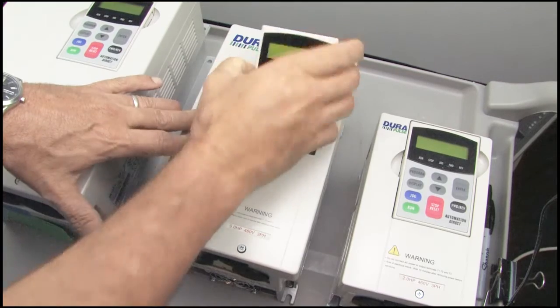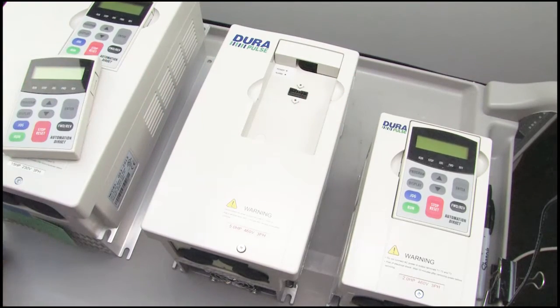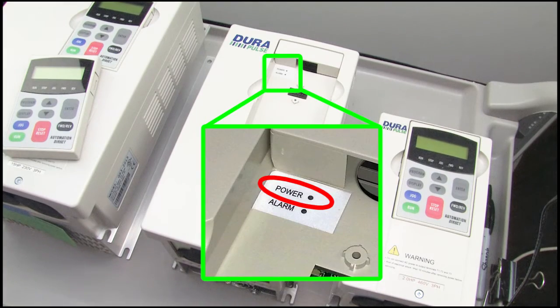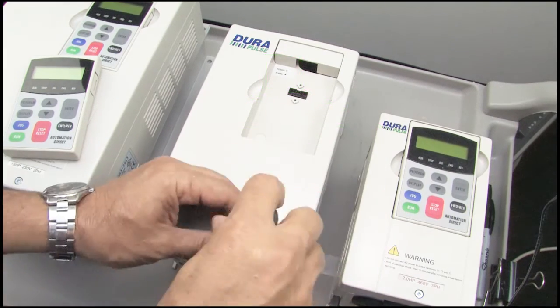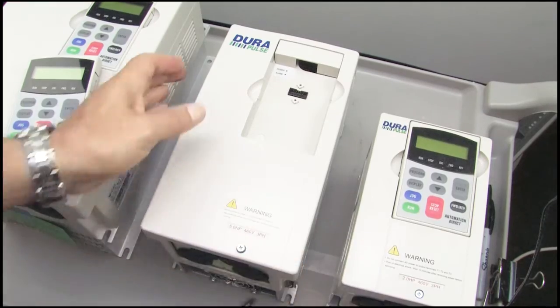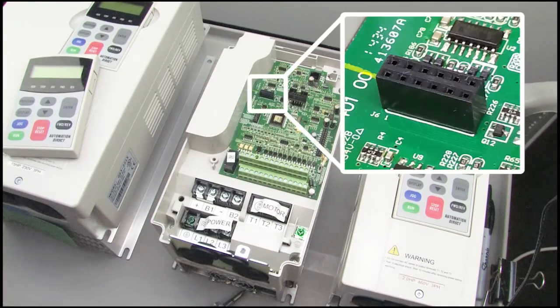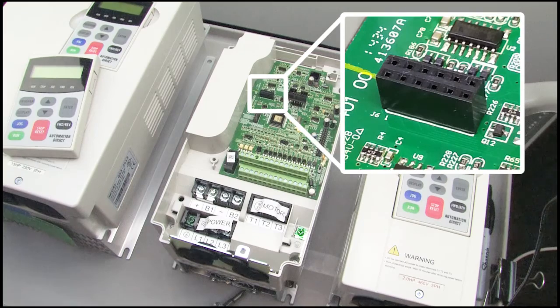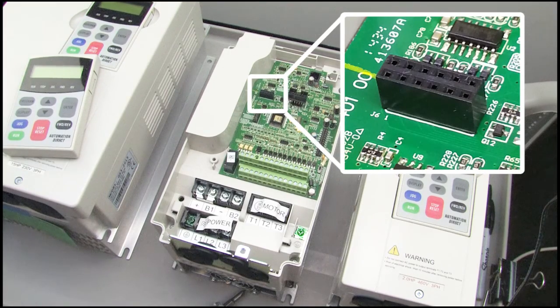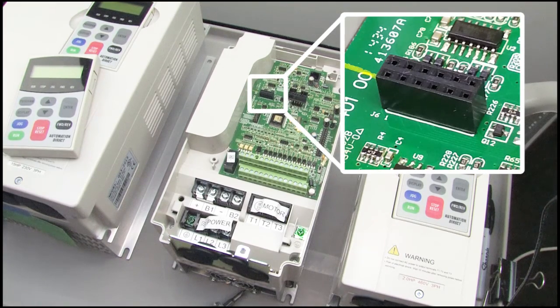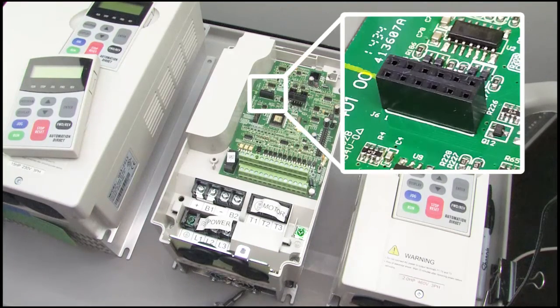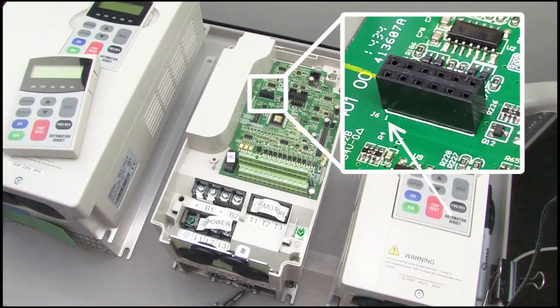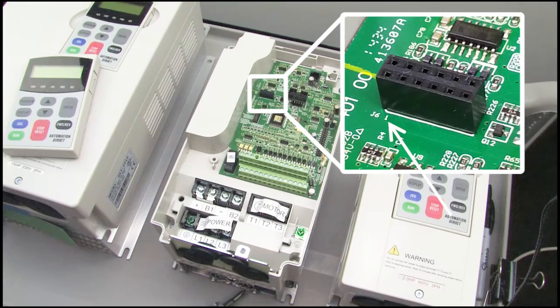Make sure the drive is not powered and then remove the keypad. If this red power LED is still lit, the drive still has potentially dangerous voltages on it. Wait for that light to go completely out. Remove the drive cover and locate the 2x6 female header. There are three different controller boards used in the different sized drives, but there is only one 2x6 female header like this one on each controller board and they all have this little white number 1 marking where pin 1 is on the header.